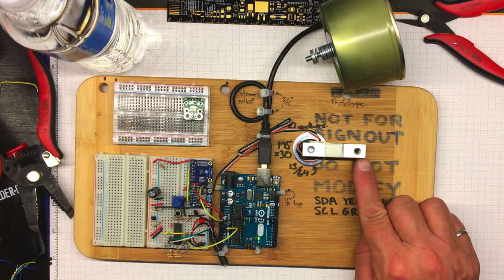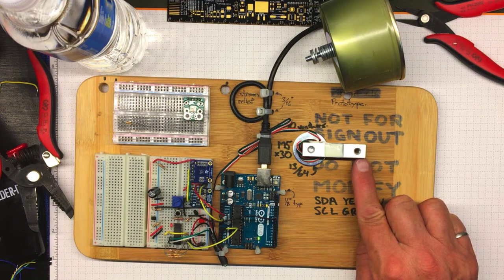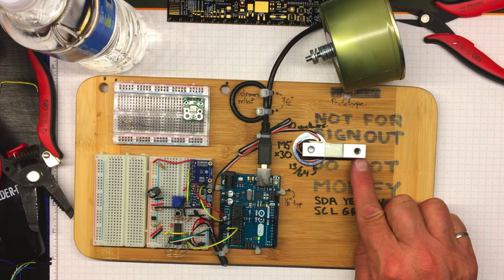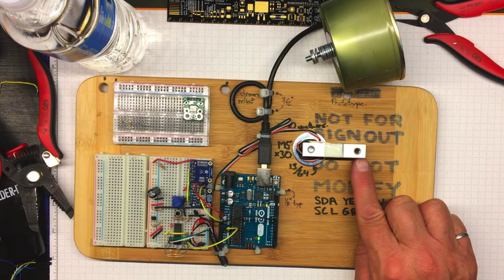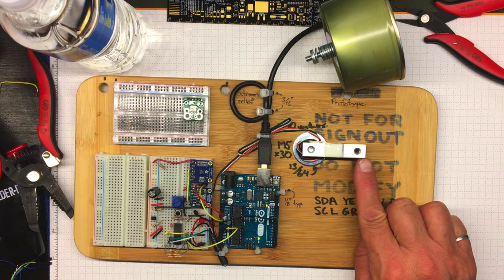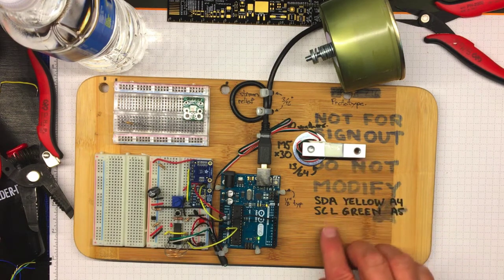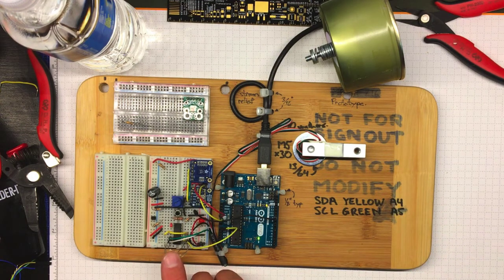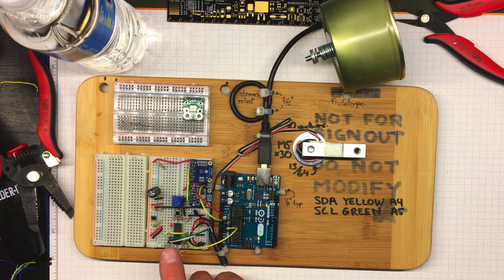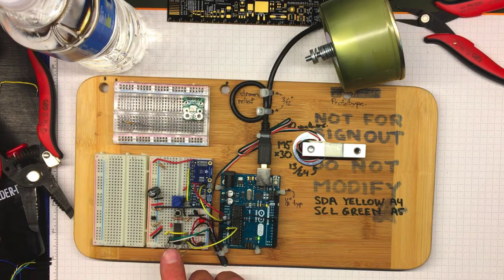It's only going to change one millivolt per volt for the full load capacity of this load cell, which is 20 kilograms. So if I want to get a signal of any size, I'm going to need a fairly high gain on my amplifier.